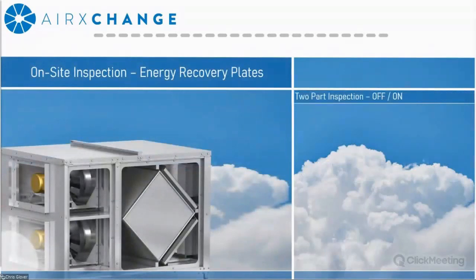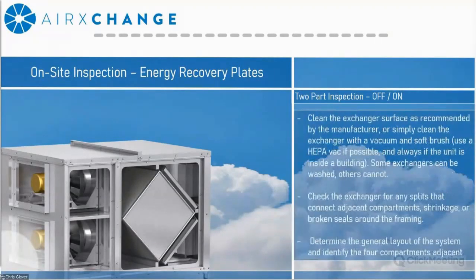So now moving over to static plates. Once again, another 2-part process. It's very similar to a wheel. With the system off, you're going to want to make sure that the unit's clean. Once again, follow the manufacturer's instructions. Typically, you can either wash or vacuum it. But after you go through the cleaning process, you're going to want to see if there's any potential shrinkage of the media or any broken seals around the framing. Once again, use that flashlight trick to see if there's any gross leakages. And at this point, you're going to want to identify the system layout and identify that in the chart that's provided.